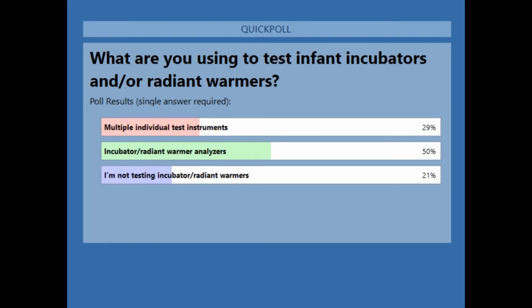And if you follow most of the manufacturer guidelines, they are also having people test to the standards. So people have to get very creative with the individual test devices they're using to test their incubators and radiant warmers. With this, you don't have to do that. It's all there, you just open it, set it up, it takes a few seconds, and you're ready to go.